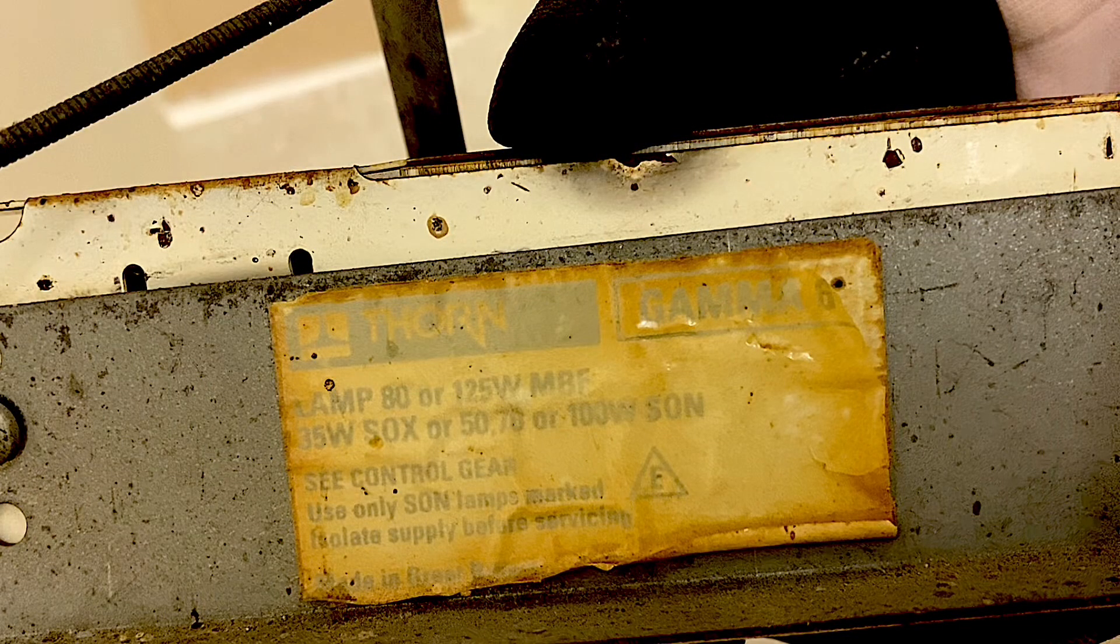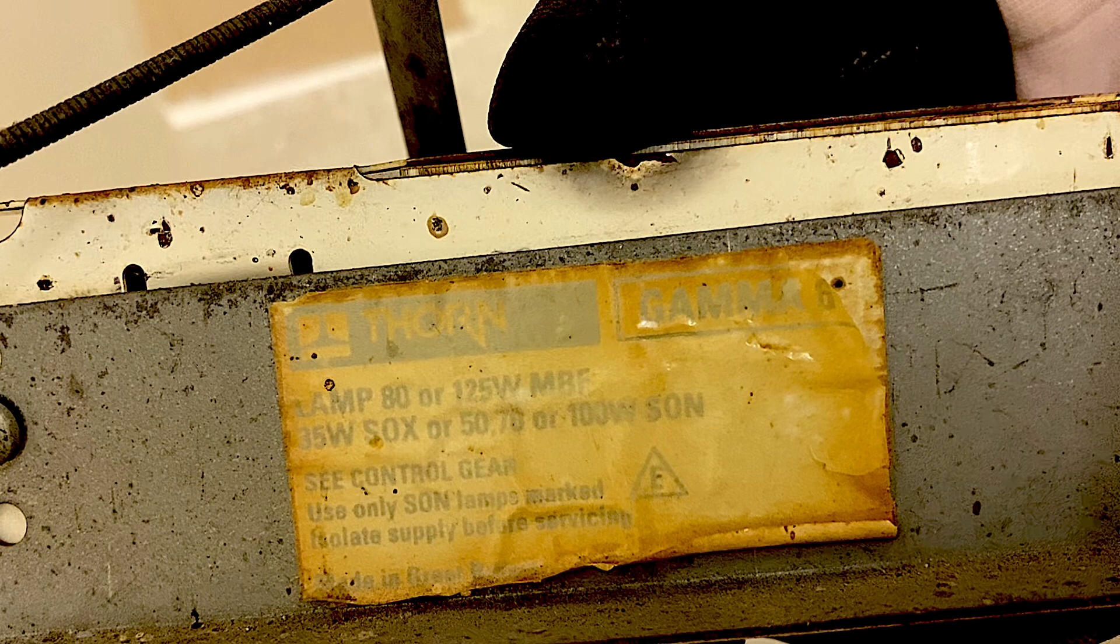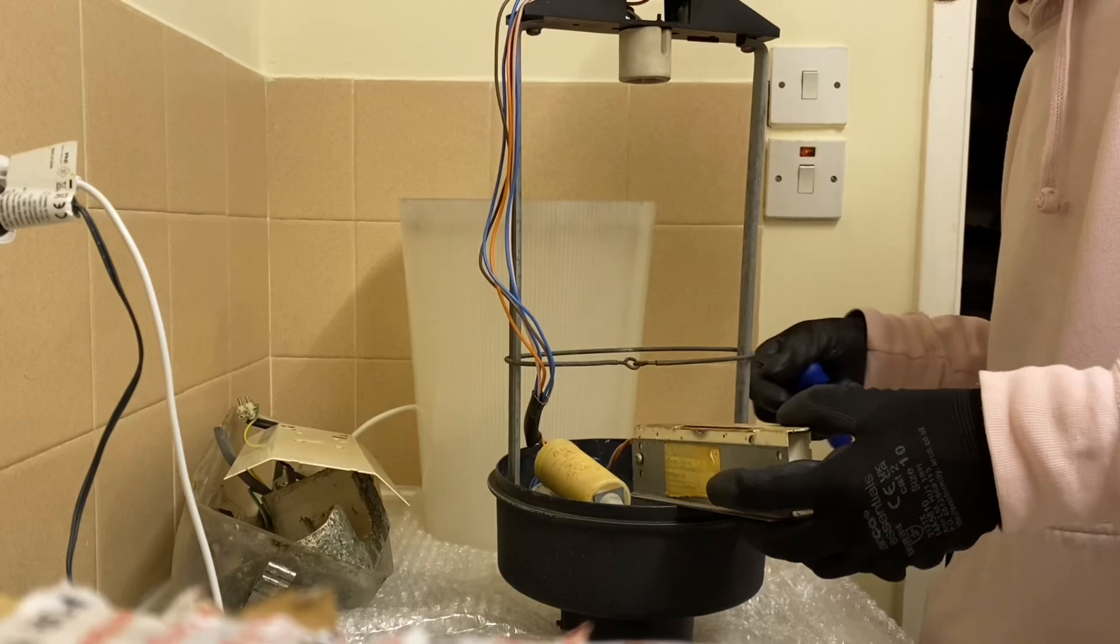But what there is, is the sticker. Thorn Gamma 6 lamp: 80 or 125-watt MBF, 35-watt SOX or 50, 70 or 100-watt SON. See control gear. Use only SON lamps marked E, which is elliptical. Isolate supply before servicing. Made in Great Britain.